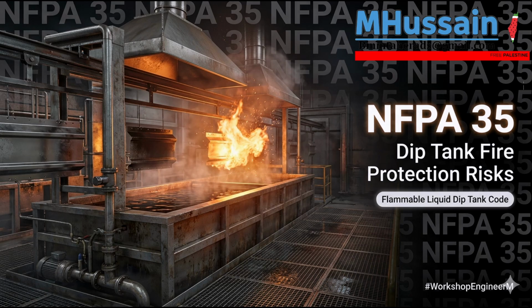Frictional heat. Wait, so we aren't just worried about an electrical arc or an open flame. We are worried about the physical act of rubbing two things together. Precisely. And this dictates exactly how operators must handle the material. The standard is incredibly blunt. You absolutely cannot drag, push, or slide a metal drum of nitrocellulose across a hard concrete floor.